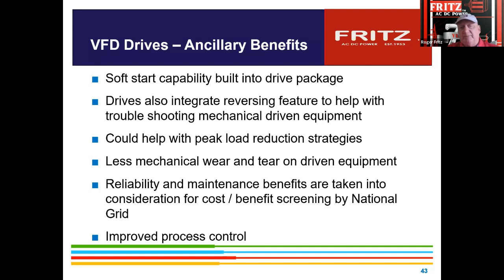Drives create a soft start capability, which helps with the original inertia into the motor. Some are used for peaking load reduction, so you can literally take some parts of your load down without having to shut the machine off, like your chillers. You can just drop them back to maybe 80%. It may raise the temperature in the building, but you can get some incentives back for that for a facility. So we can help you with how to do that, where they're looking for additional peak shaving money.